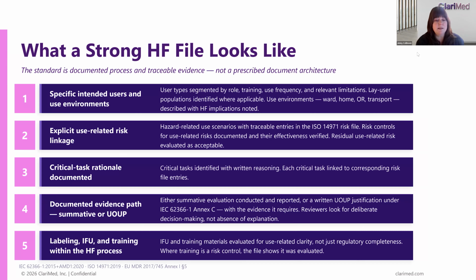And finally, but certainly no less important, in legacy files, IFU and training is often being treated as a regulatory output. And MDR is very clear that they're part of the human factors process and need to have been evaluated for use-related clarity. And it could be very simple, it could have already been done as part of formative assessment, but it's a gap that needs to be considered and documented. And if it's not present, then it will prompt questions.